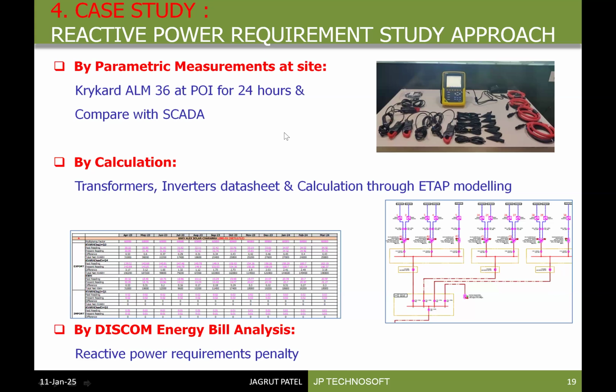Then the second method was by simulating the system on network analysis software like ETAP. So we modeled the entire scheme on ETAP, starting from the evacuation point up to the last point of solar. And then the third methodology was energy bill analysis.